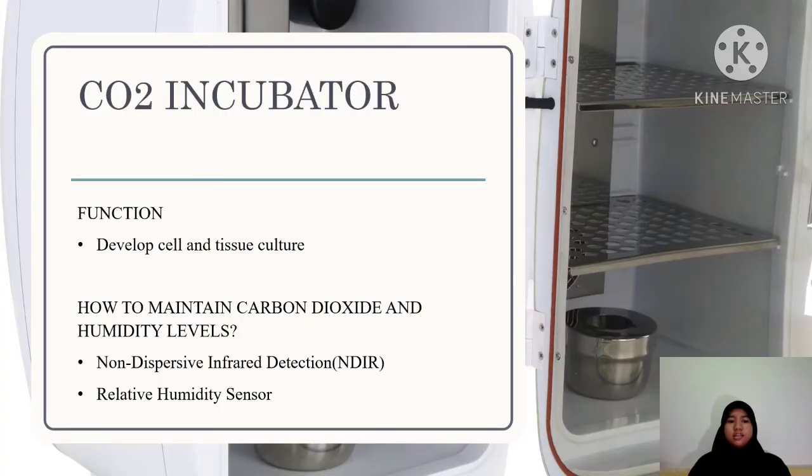Next, the first medical equipment that uses a sensor is the carbon dioxide incubator. The function is to develop cell and tissue culture. It is used to create an atmosphere. It must maintain carbon dioxide and humidity level.